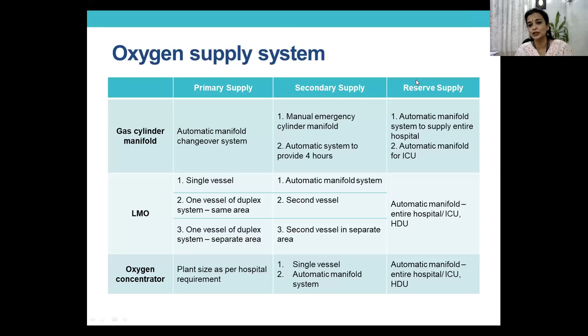Now, this is something about our network. What is the kind of backup that we have? We have 3 liquid medical oxygen plants, 11 KL, and we have 2 separate lines coming from these 3 LMO tanks, 33 KL in total. Then they go to separate buildings. So each building, if one fails, it doesn't mean the other building is going to fail. The other one takes over. And we have about 4 manifolds in strategic locations in our hospital that can take on the load for up to 4 hours. And we also have a concentrator that can actually take over the load of LMO, or it can connect separately to 2 buildings.